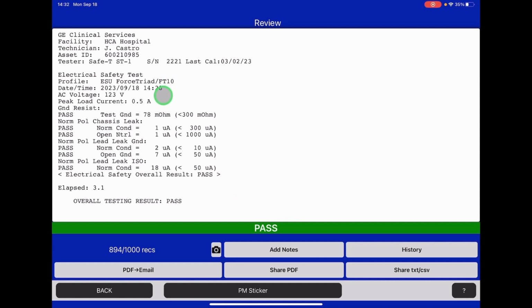And here in the center are all of the tests we ran, your measured values here, and then your test limits, your pass-fail limits here on the right. So we've completed the electrical safety testing on this FT10 ESU analyzer.